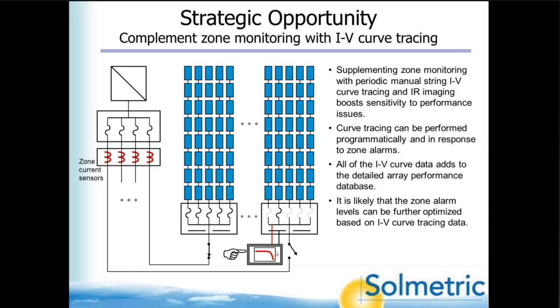And there are a couple of reasons for taking this approach. One is if your zone monitor tells you that a particular subarray is a little bit low, you can go out there with your curve tracer and measure those strings and know exactly which strings are causing that issue and chase it down to what the issue is. It gives you a better understanding of what's bothering your array. And it gives you a better understanding also of how sensitive your current sensors are. In other words, are they set at the right level to detect the kind of problems that you want to detect?